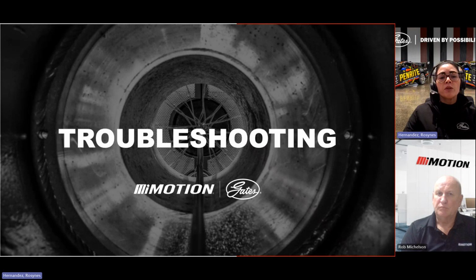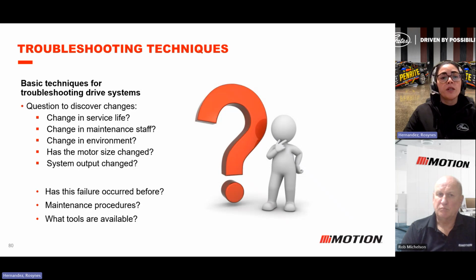Okay, on troubleshooting, the basic techniques: you need to check in your drive if there is any change in your maintenance staff, which is very important. If the service life is different, or if the environment where your belt drive is located has changed. Also check if the motor size, the condition, or the parameters of your belt drive have changed, and if your output parameters have changed as well. Sometimes you upgrade your belt, and once you upgrade it, you need to test that the belt will perform based on your new parameters, especially for those machines that are really old. So always check that.